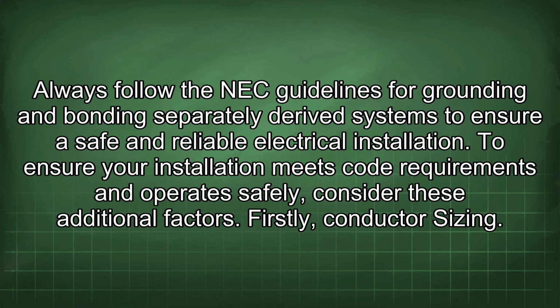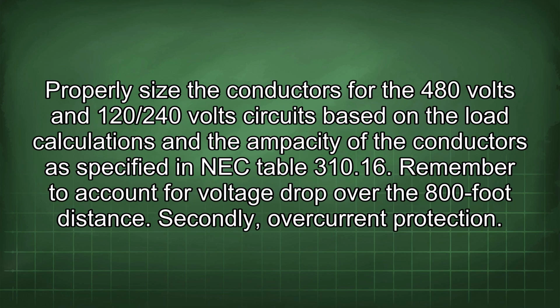To ensure your installation meets code requirements and operates safely, consider these additional factors. Firstly, conductor sizing. Properly size the conductors for the 480 volts and 120/240 volts circuits based on the load calculations and the ampacity of the conductors as specified in NEC Table 310.16. Remember to account for voltage drop over the 800-foot distance.